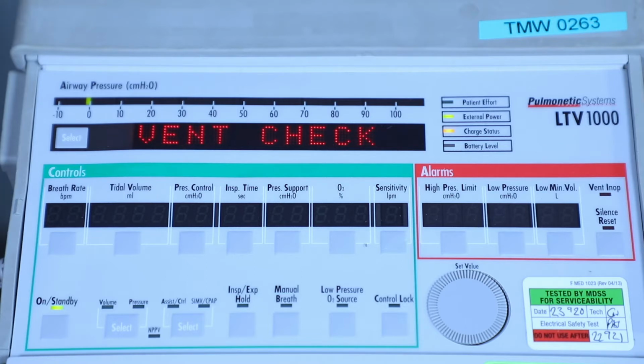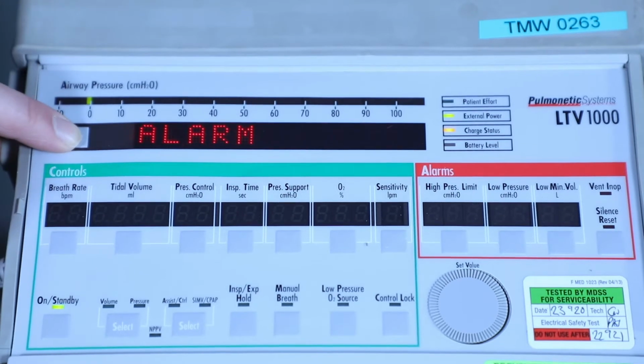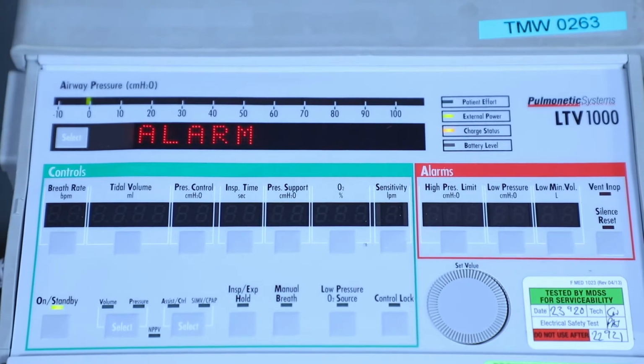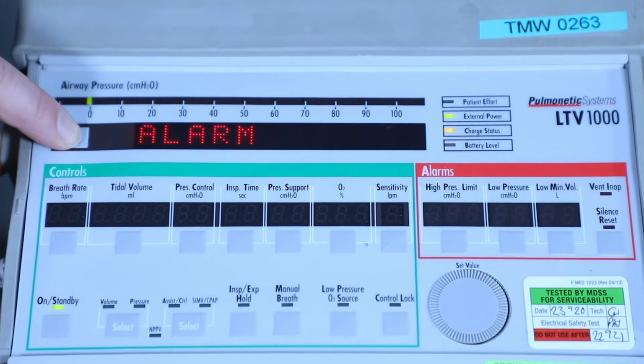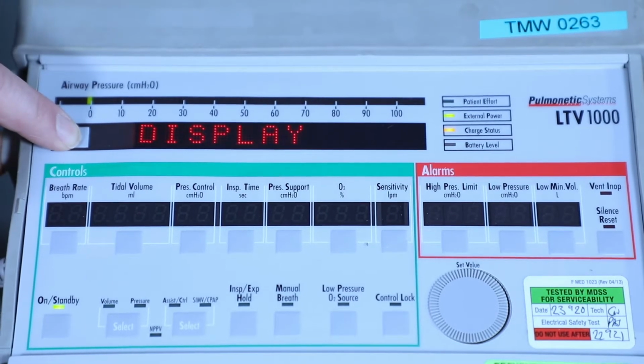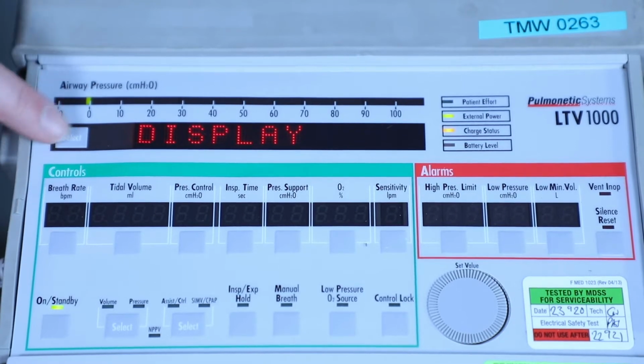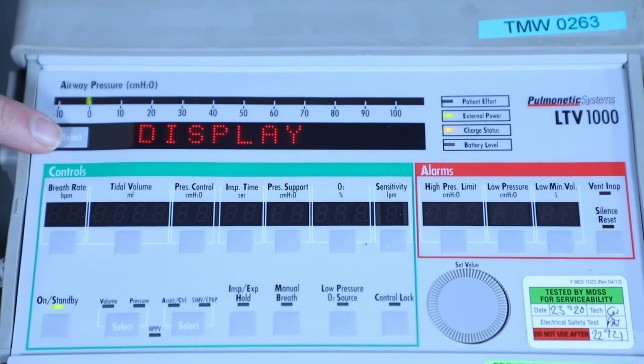Now that the device is in test mode, the first menu that we see is vent check. We want to enter this using the select button. Press the select to enter the alarm, and this tests the audible alarm. Press the select button to move on to the next item to check, which is display.